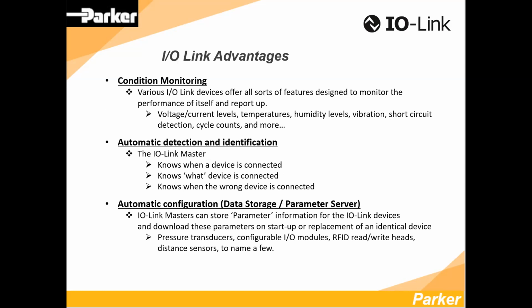We've been talking about condition monitoring from the very beginning. This is what IOLink smart sensors provide - basically they give you information about themselves: voltage, current levels, temperatures, humidity, vibration, short circuit detection, overload detection, cycle counts - all maintained internally and not done in a PLC or robot enclosure.